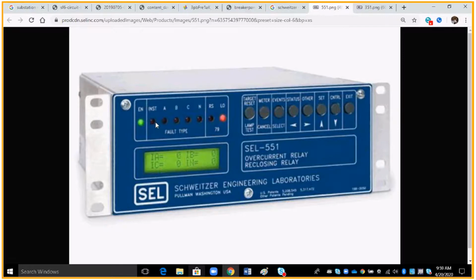It'll tell you actually here if you had a fault on A, B, or C, or neutral. We'll talk about how you can get a fault on neutral in just a little bit. But they're pretty easy to read, and like I say, ask questions. If somebody asks what the current reading on A is, that's pretty simplistic. Do you have a fault on B? That red light will be up. Are you in local or remote? There's a lot of different stuff you can ask questions about if you are asked to go into a substation and check something out.